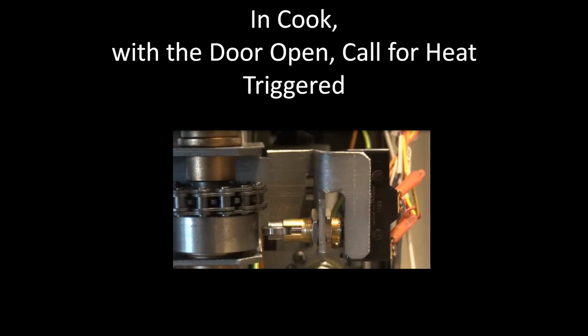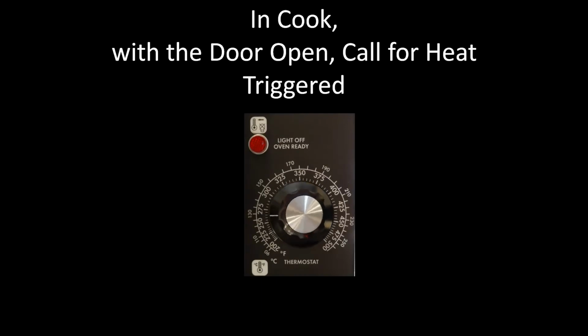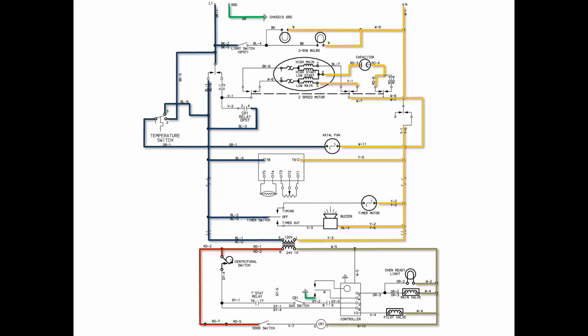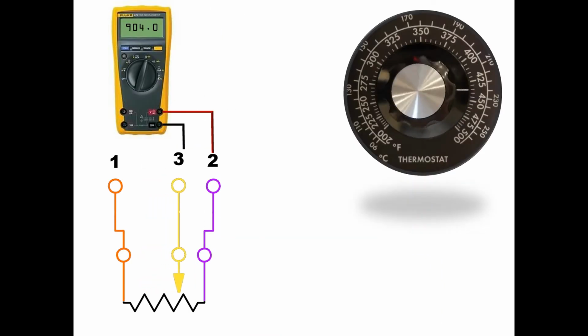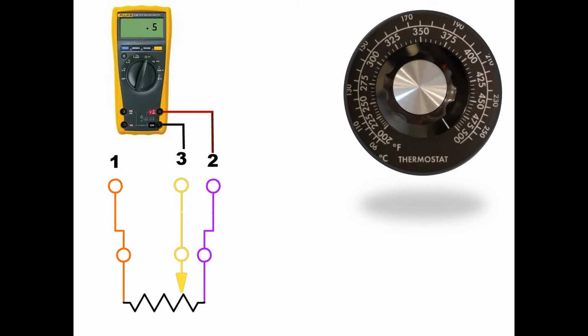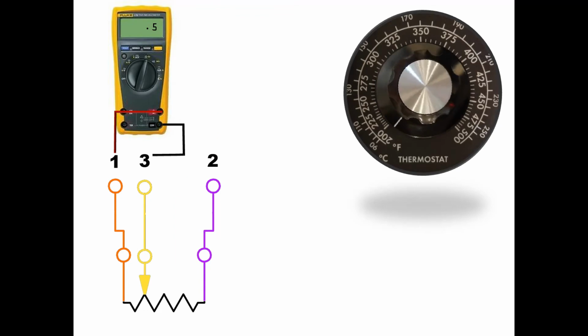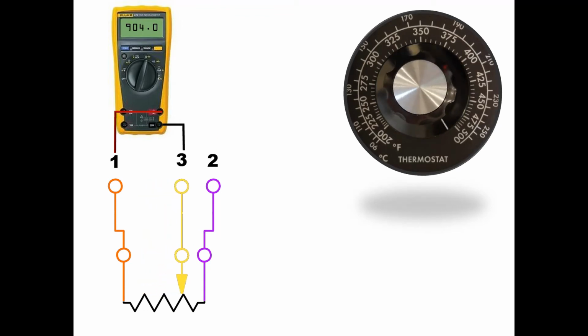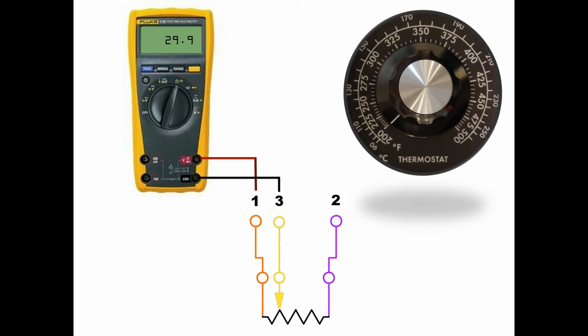Next, in cook, we will trigger a call for heat with the door open. The temperature control board, the potentiometer, and the probe control the call for heat. When turning the potentiometer up, hooked to yellow and violet, the reading will go from high to low. When turning the potentiometer up and hooked to yellow and orange, the reading will go from low to high. As the potentiometer is turned, the ohm should smoothly increase with no shorts or open segments.